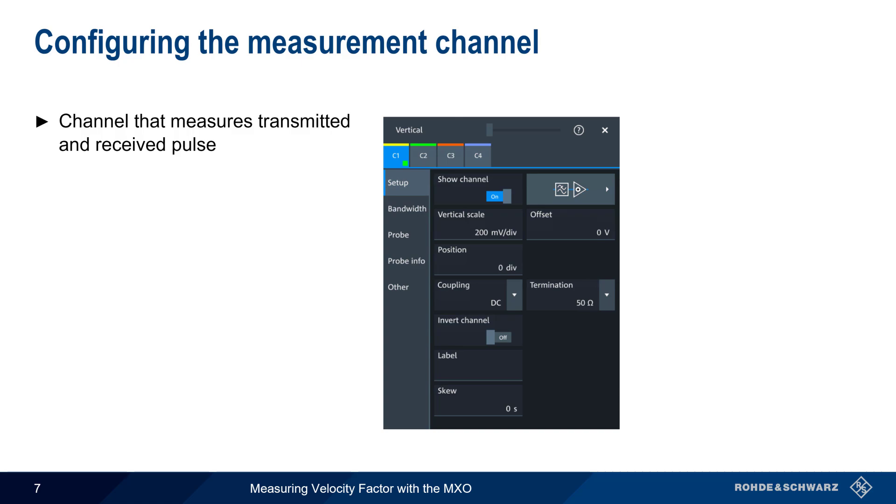Next we need to configure the measurement channel. This is the channel that measures the transmitted and received pulse. First, the channel termination should normally be set to 50 ohms in the setup menu in order to match the generator impedance. If necessary, the vertical scaling or volts per division setting should also be set appropriately.